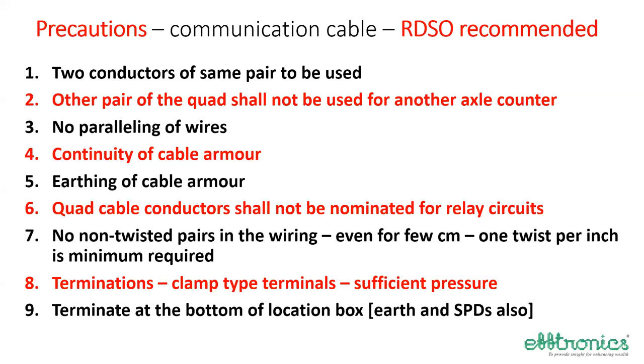No non-twisted pairs in the wiring, even for a few centimeters. One twist per inch is the minimum required. As I was telling, after the quad cable is terminated, when we are taking it to the equipment rack, there we have to use twisted screened cable only. Terminations shall be clamp type terminals with sufficient pressure. It shall not be screw type. Terminate at the bottom of the location box. Because if you take these terminals to the top, the conductor gets exposed to the other conductors where signals of high voltages may be available.